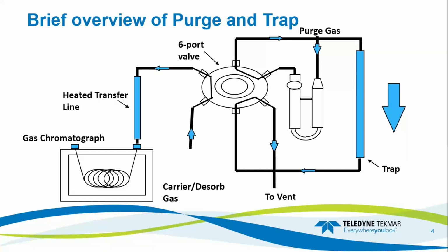A basic purge and trap consists of five main parts: the sparger, flow control, six-port valve, analytical trap, and the heated transfer line. The sparger is the glassware on the front of the instrument that receives the liquid sample to be purged.